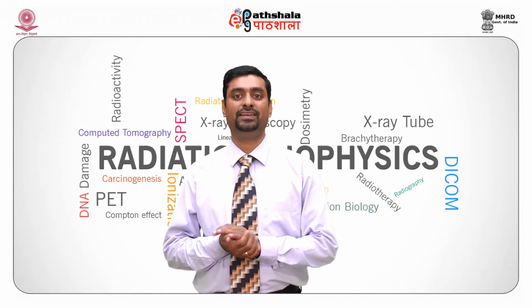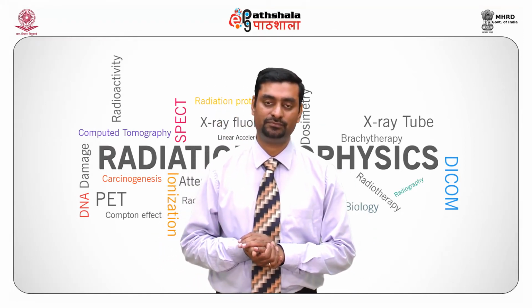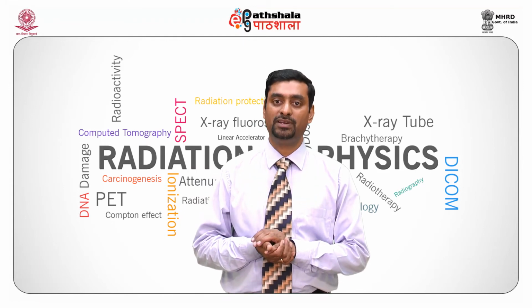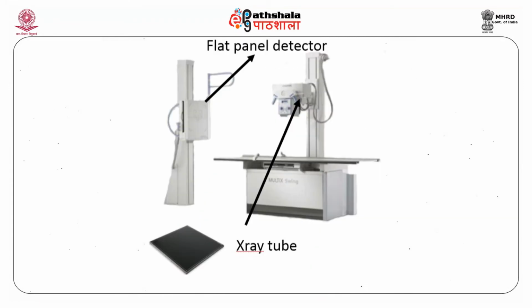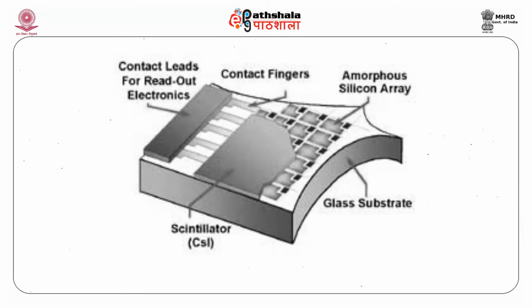The second part of the indirect conversion flat panel detector is the amorphous silicon based technology. The general principle of this amorphous silicon technology is that when X-rays fall onto the patient, the transmitted X-rays fall onto a scintillation material. Here too we see it may be a 17 by 14 inch area which has the scintillation crystals.